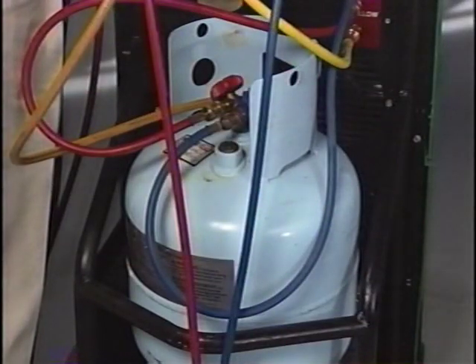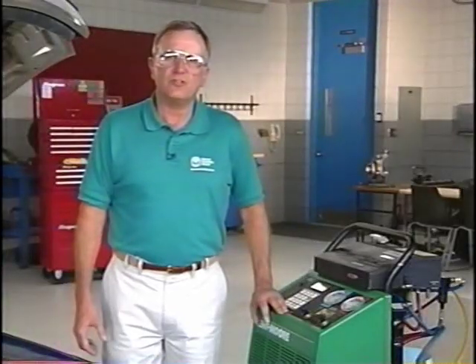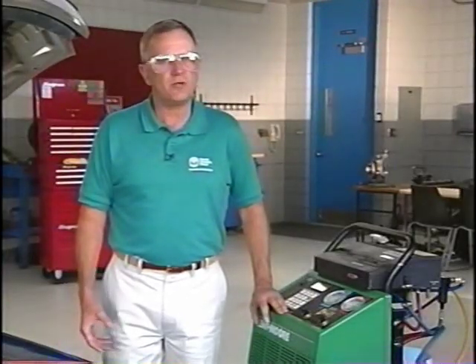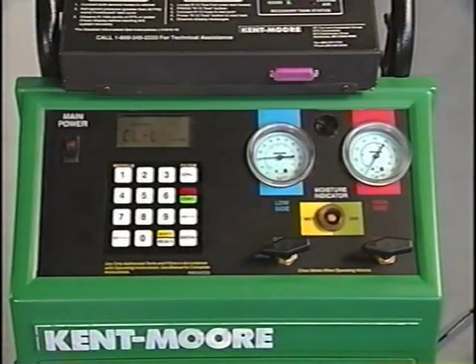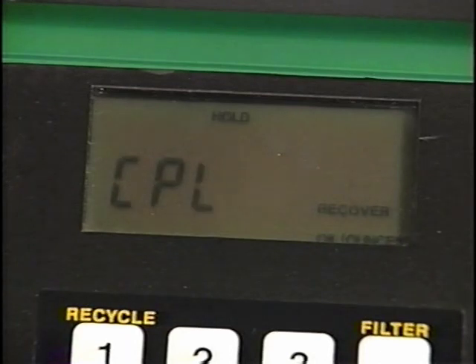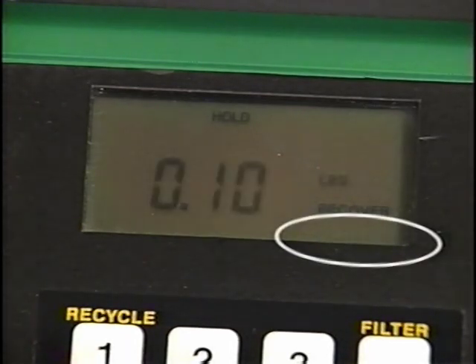During the recovery process, the machine is going to be clearing the lines. That process takes 30 seconds to 3 minutes. During that process, the letters coming up on the panel will say CL-L. The ACR4 separates the oil as it operates. The flashing oil ounces is a reminder to always drain the oil from the system at this time.